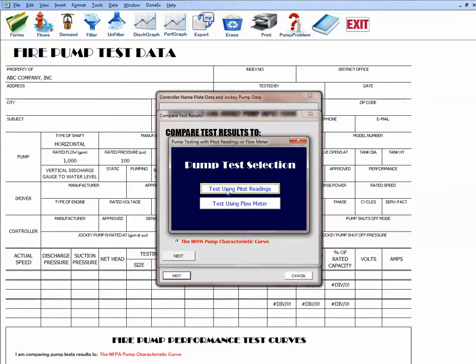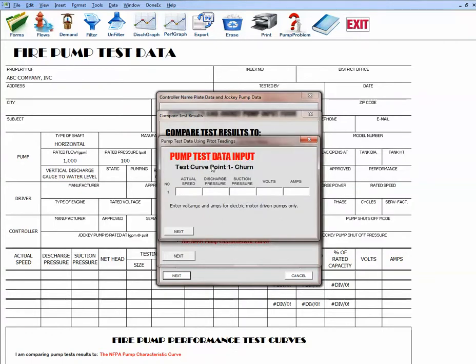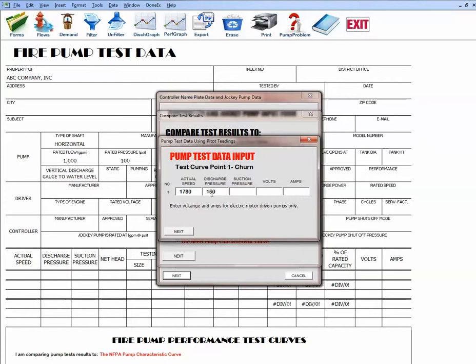We select testing using pitot readings or flow. A window prompts entry of water flow test data — for churn, for the first point, plotting three points. We'll enter the actual RPM; let's say it matches the pump rated speed of 1780. If actual RPM differs, the program adjusts flow and pressure accordingly. The discharge pressure is 150 psi, suction pressure is 30 psi, voltage is 210, and amperage is 40 amps.